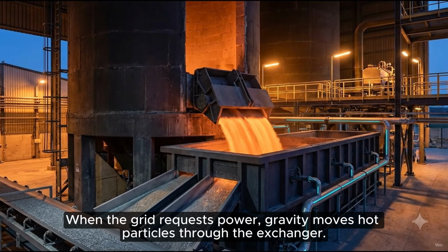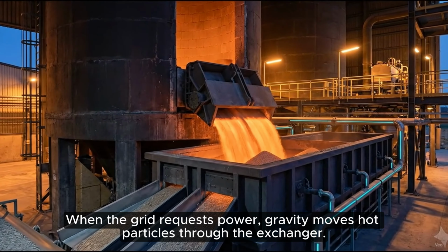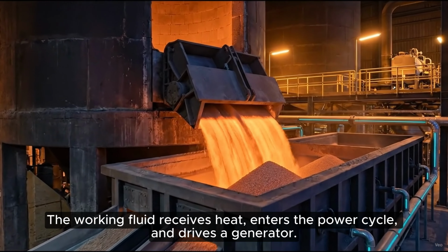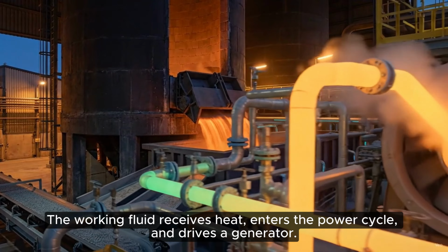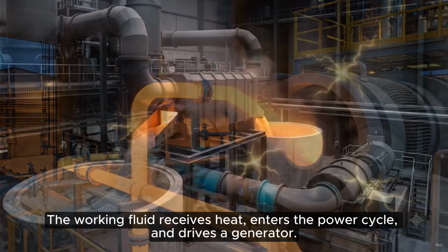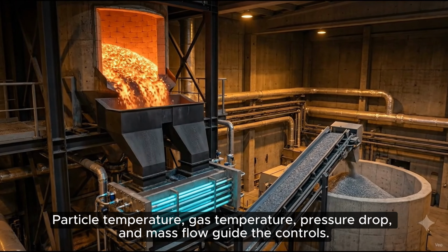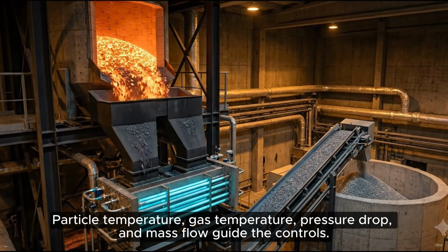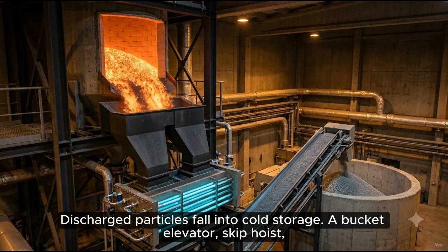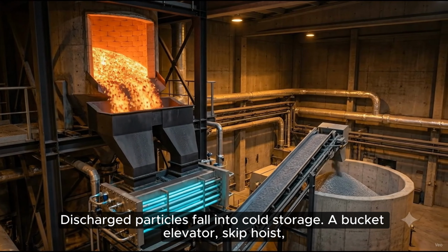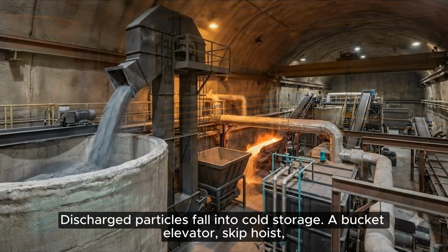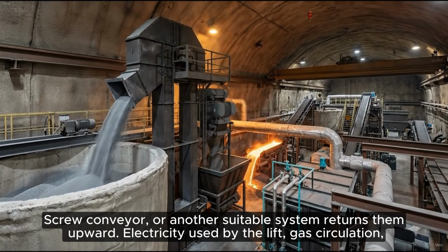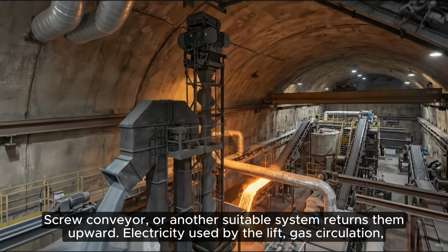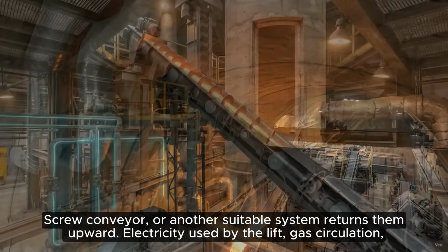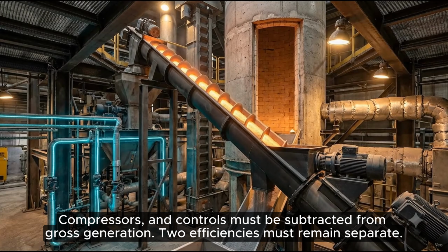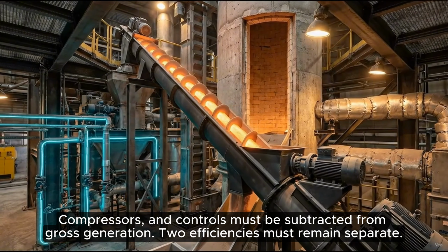When the grid requests power, gravity moves hot particles through the exchanger. The working fluid receives heat, enters the power cycle, and drives a generator. Particle temperature, gas temperature, pressure drop, and mass flow guide the controls. Discharged particles fall into cold storage. A bucket elevator, skip hoist, screw conveyor, or another suitable system returns them upward. Electricity used by the lift, gas circulation, compressors, and controls must be subtracted from gross generation.